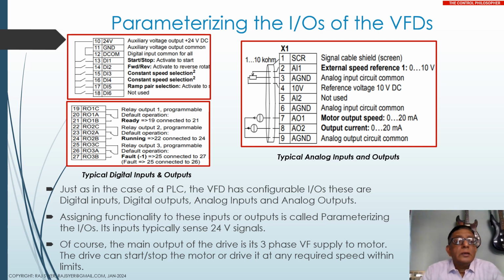Similarly, the relay outputs: the diagram at the lower left for digital output shows 3 outputs. Each of these can be assigned to a certain function. One is to show that the drive is ready, or when it is running, or when there is a fault. These are potential free. They can be wired up to an external indicator lamp, or they can even be used to interlock other things, such as inputs in PLC logic.